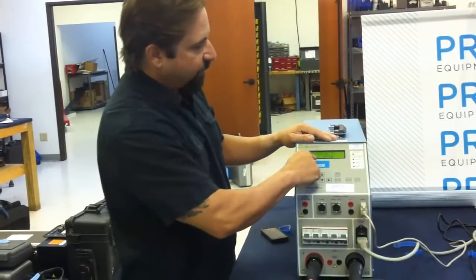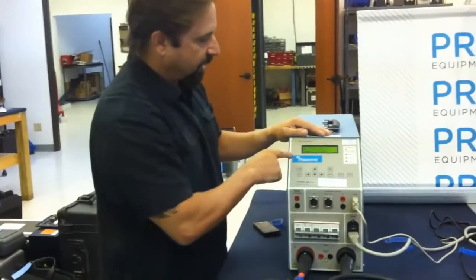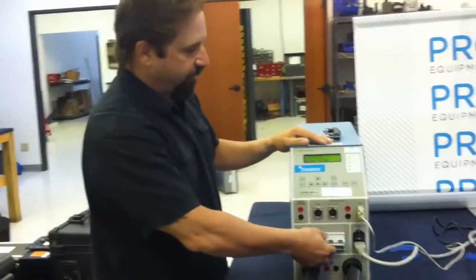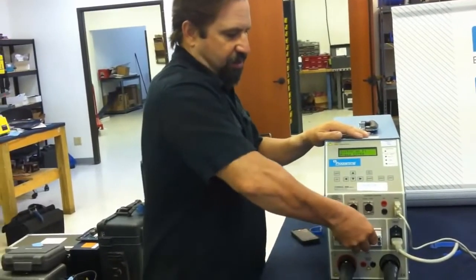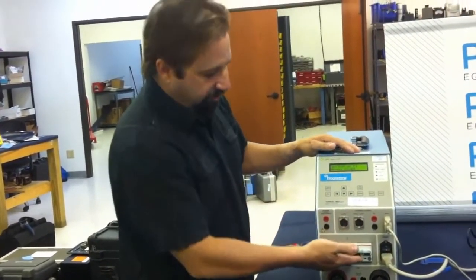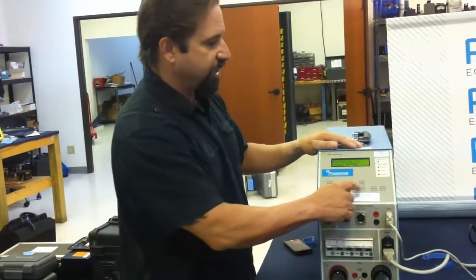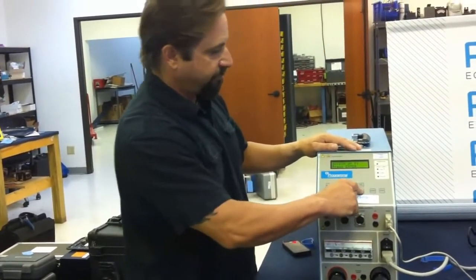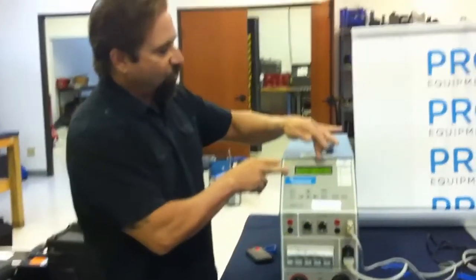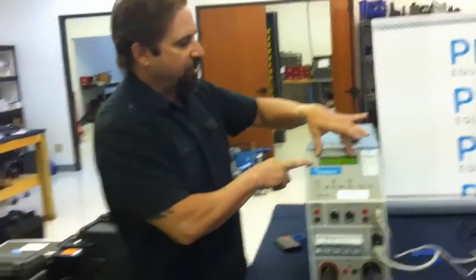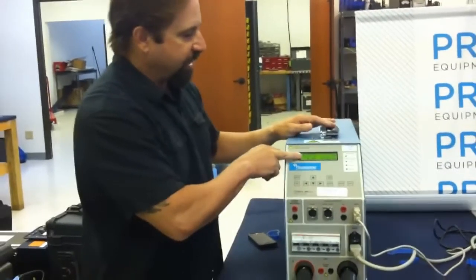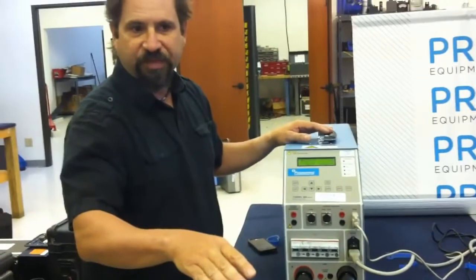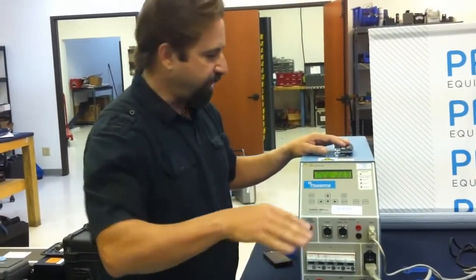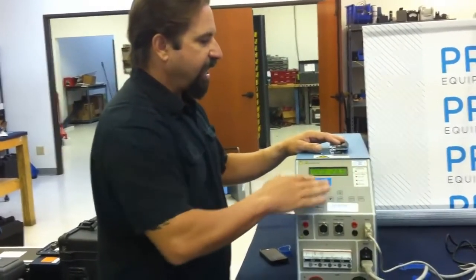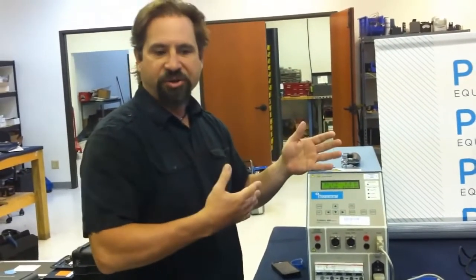Next it will say switch on the F1, or your main circuit breaker. So we set our F1 switch or main breaker switch and hit enter. The TORKEL will now sit at the monitoring screen. It shows I have 51 volts on my 48 volt battery bank, but I haven't actually begun to run the test yet.